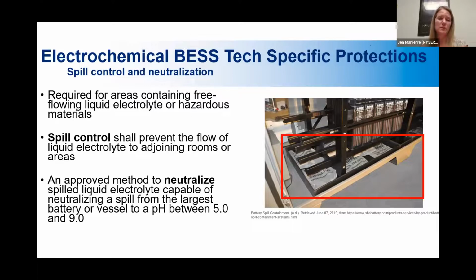The spill control and neutralization. This is not a requirement that applies to lithium-ion batteries, but the fire code covers all of the different technologies, and some batteries have liquid electrolytes in them, which presents the opportunity for a spill if something goes wrong. So for those batteries, one of the safety compliance mechanisms in the fire code is spill control. They need to have some sort of containment under the batteries to catch a spill, not just catch the liquid, but neutralize it to an appropriate pH level as well.